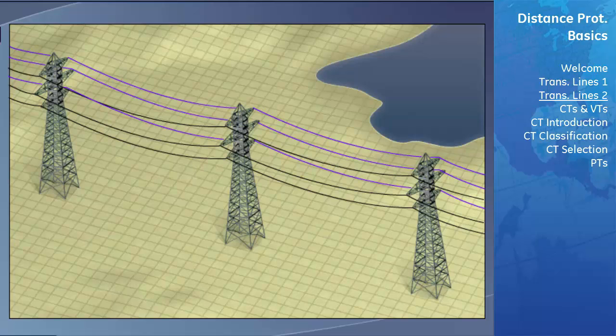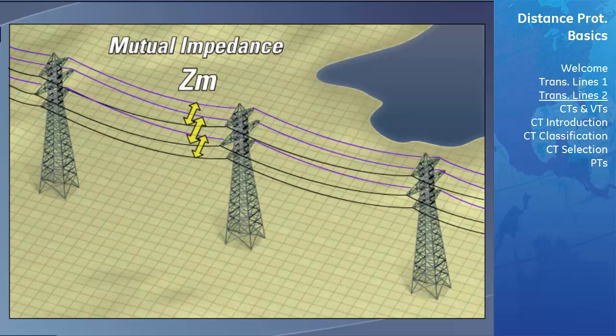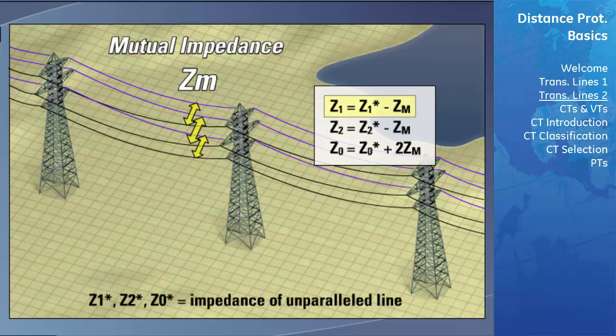When multiple transmission lines are aligned parallel to one another, their interactions induce an impedance on each other known as the mutual impedance, notated as ZM. When this occurs, the overall sequential impedances are affected as follows: the positive sequence impedance becomes the positive sequence impedance of the unparalleled line minus the mutual impedance; the negative sequence impedance becomes the negative sequence impedance of the unparalleled line minus the mutual impedance; and the zero sequence impedance becomes the zero sequence impedance of the unparalleled line plus two times the mutual impedance.